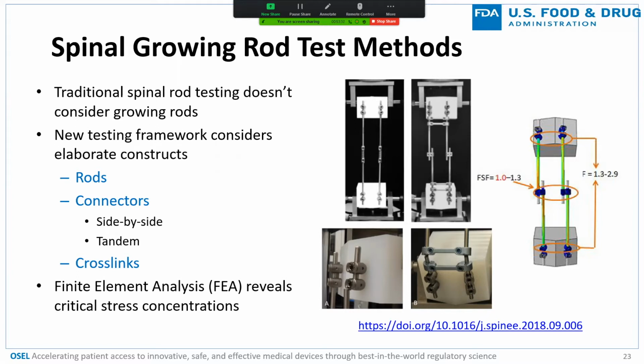And the challenge with these devices is that while the surgeon attempts to correct the deformity and allow a child's pulmonary function to resume, and actually the lungs to function to begin with, the surgeon cannot fuse the spinal column together because obviously the child is actively growing. So the devices that are implanted have to periodically, at a frequency of about 2 to 3 times a year, be adjusted, and the child will have to go through additional surgical procedures to allow for increased length of devices in accordance with spinal growth. And what happens is with these devices, the frequency of failure in clinical use is quite high, just because the overall load and the fatigue capacity of these devices sometimes is exceeded.